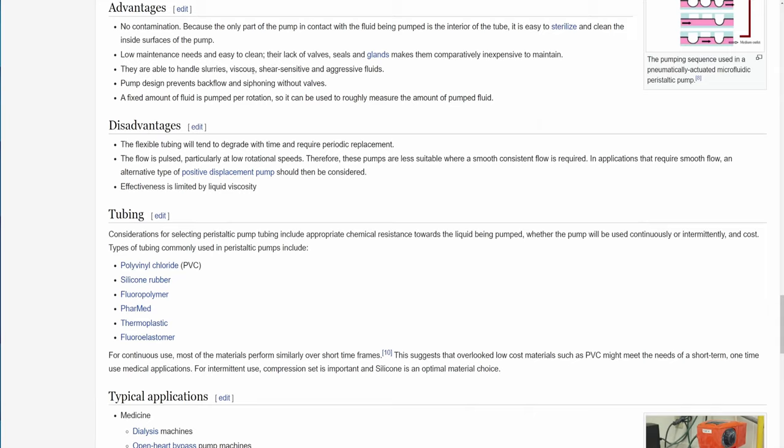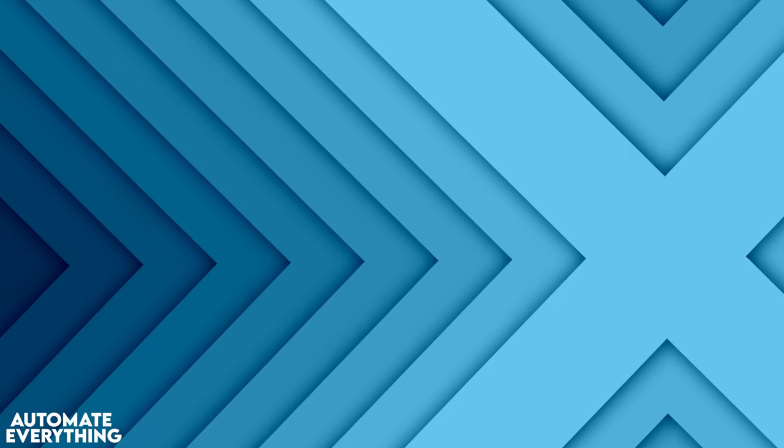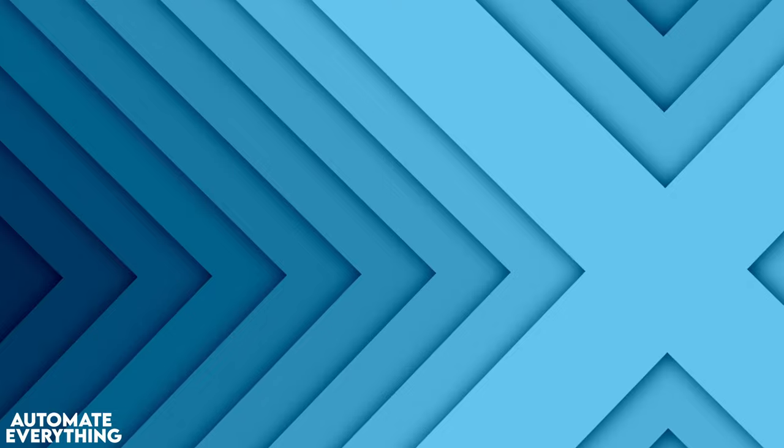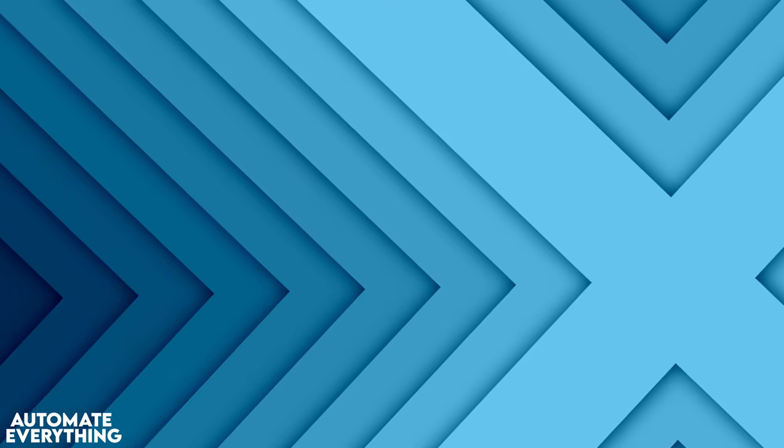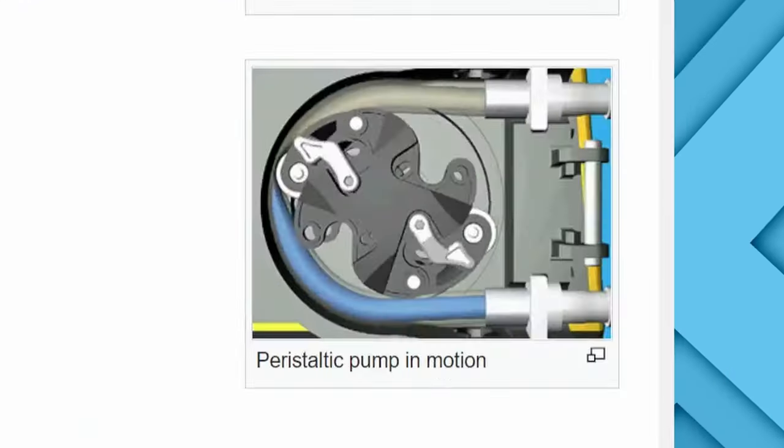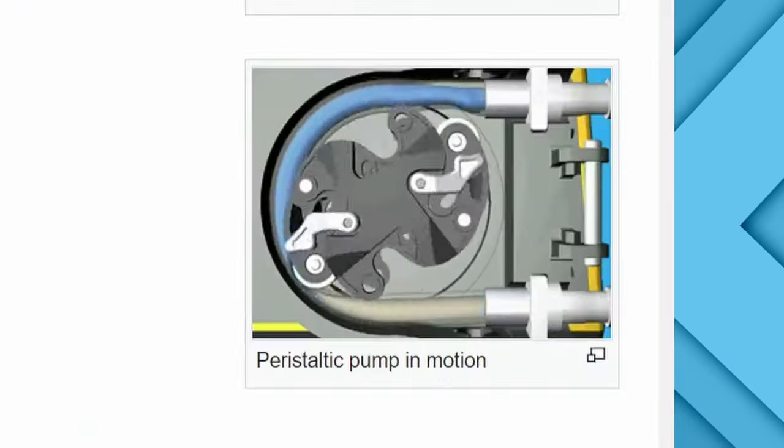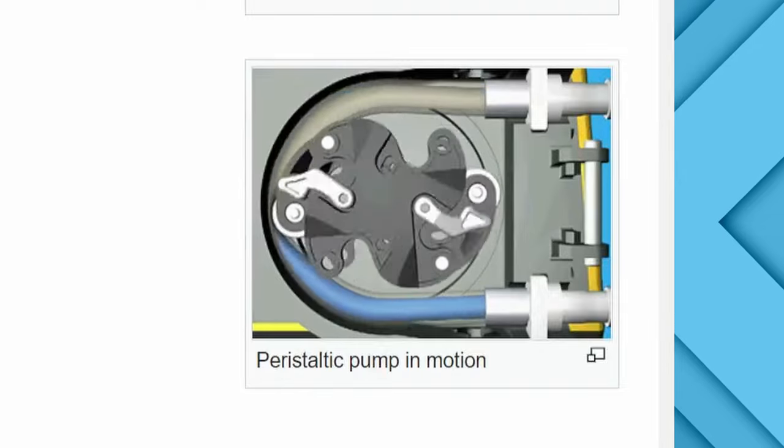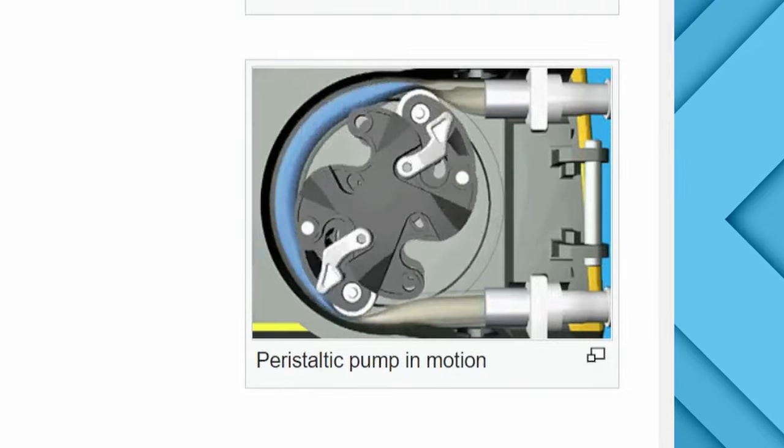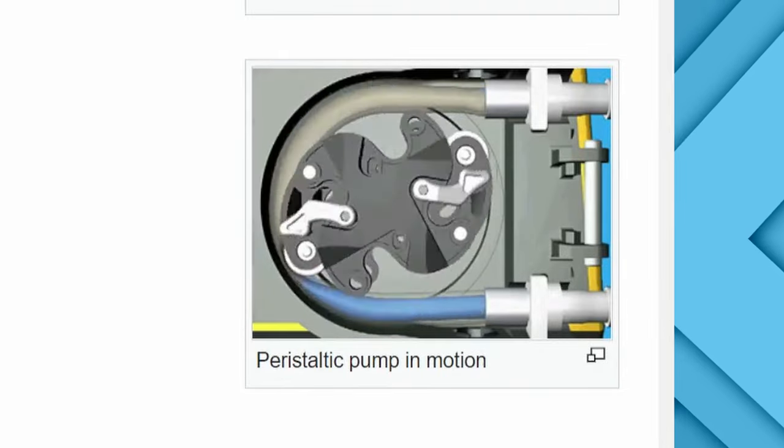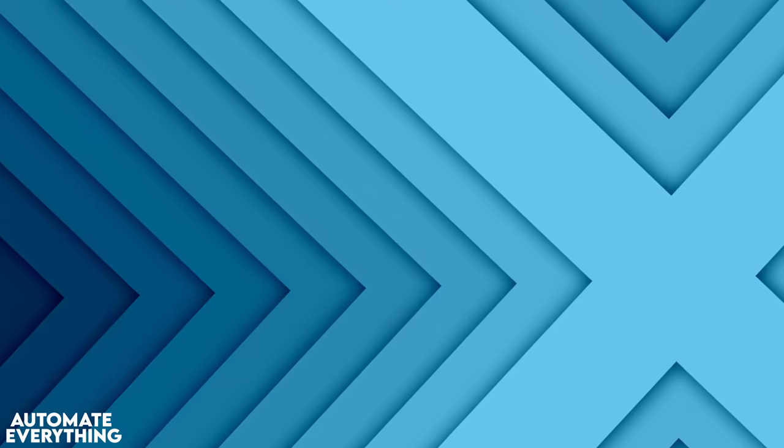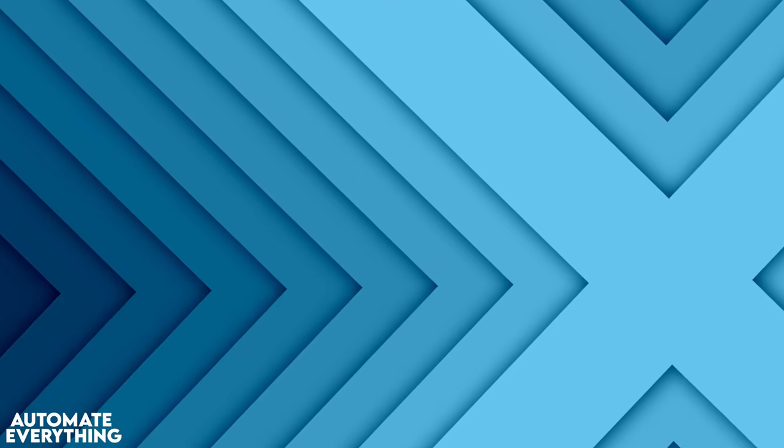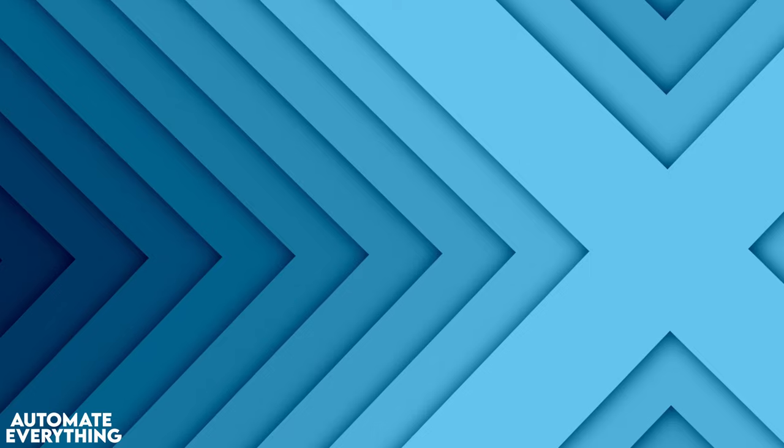Lastly a peristaltic pump is able to pump a specific amount of fluid per rotation of the rotor. It does this by creating little pockets which are separated by rollers where the fluid will be trapped until it leaves the output side. The output side can also be the input side because if you reverse the direction it will pump the other way around.